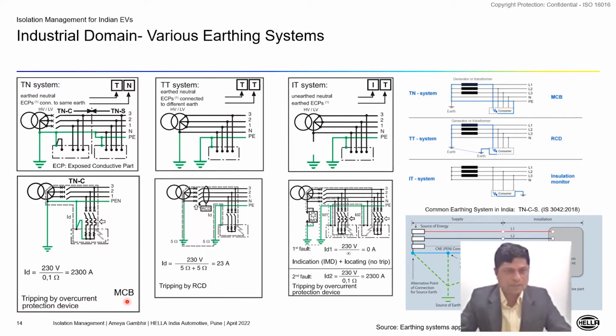So basically MCB is used in a TN system. You can see that if there is an isolation fault, then the currents flowing through that fault line will be more than 2300 amperes in this example. So obviously this will require tripping of an overcurrent protection device, and one such device is the circuit breaker. For a TT system, we use RCD, the residual current device, because here the currents are relatively low. And then for an IT system, we use IMD. So IMD is required for an IT system, and let's discuss in the next slide how it is related to our industry.